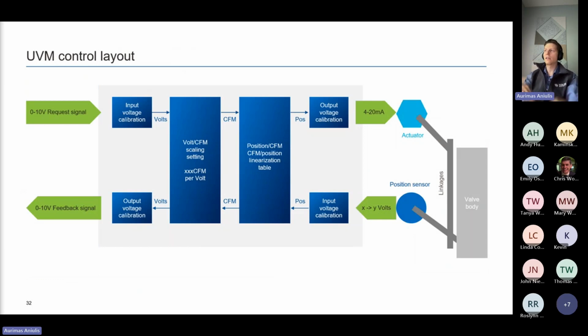Again, this is a logic layout of what the UVM does. It's fairly basic. The tables are what we populate in the factory. So we know for this device, this position at this pressure is equal to this CFM. And that gets linearized to a simple 0-10 input request command signal for your CFM and a 0-10 feedback CFM signal.